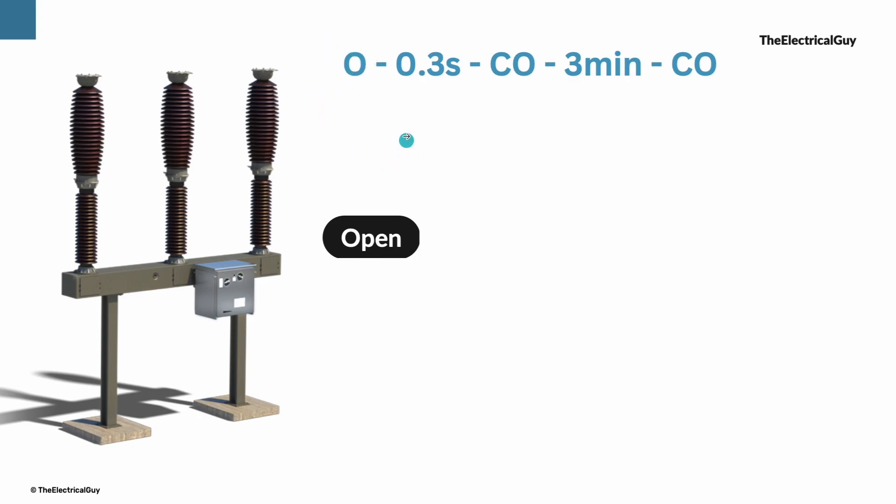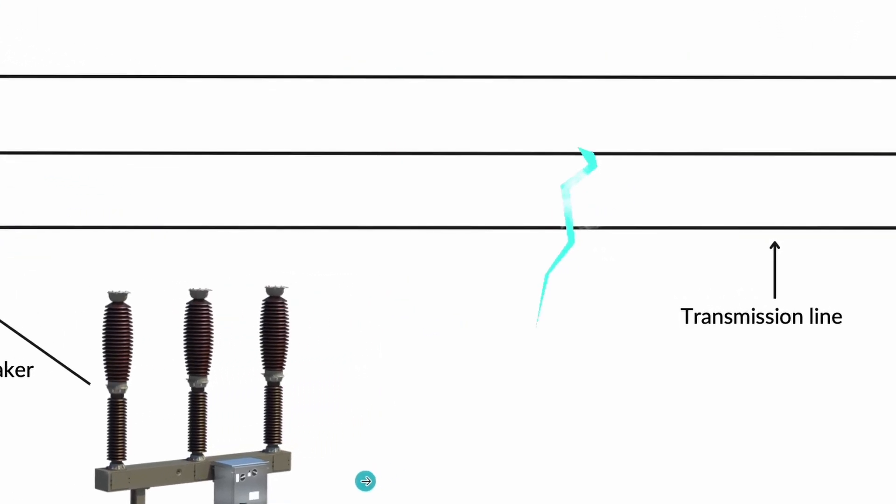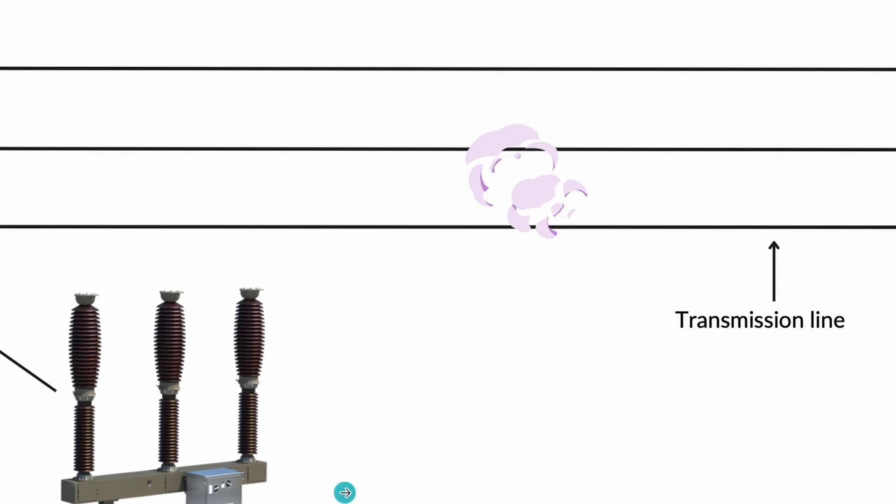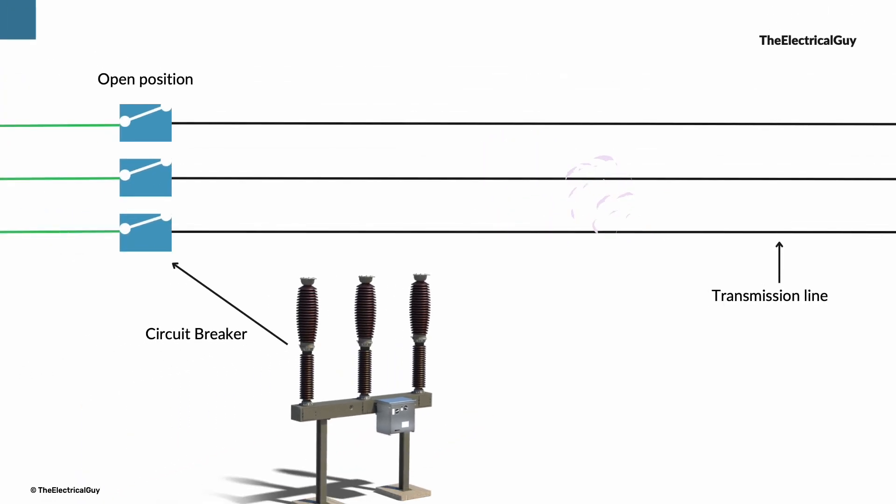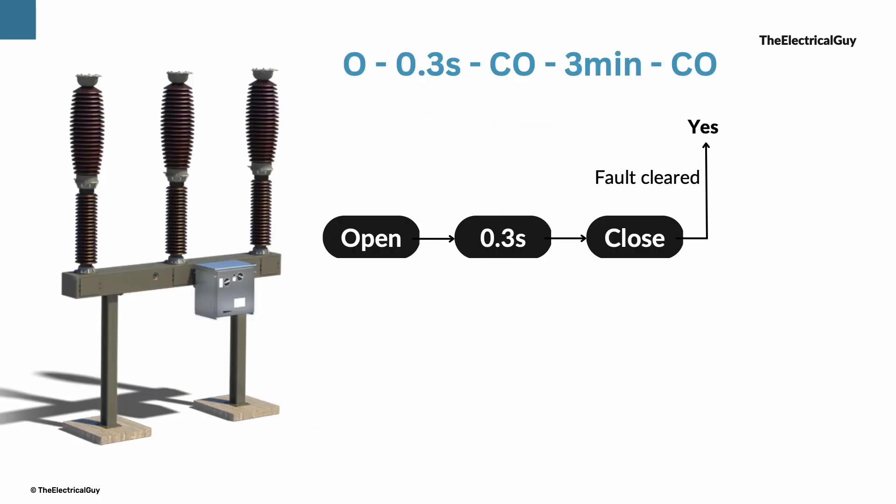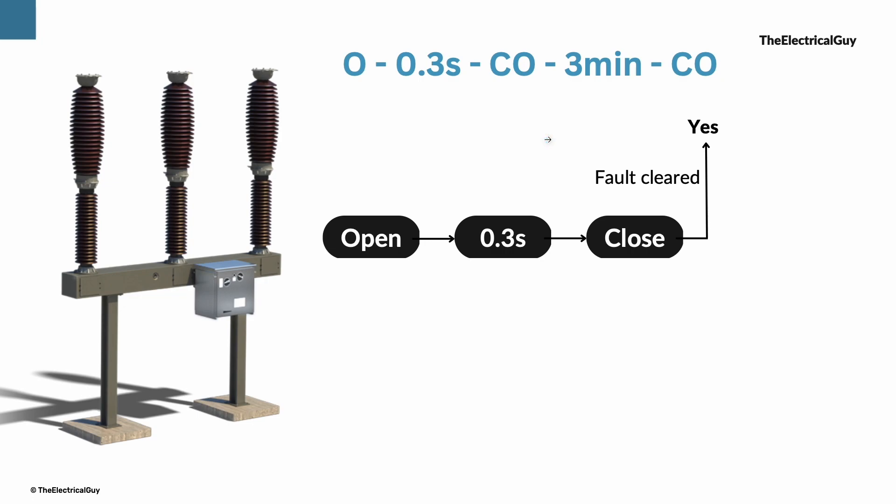And after a delay of 0.3 seconds, the circuit breaker will receive a command to close. Now 0.3 second delay is given so that the arc caused by the transient fault would go away and air will have its dielectric strength back. So if the fault is clear, the breaker will remain in the closed condition and the system is back in normal operation without any human intervention.